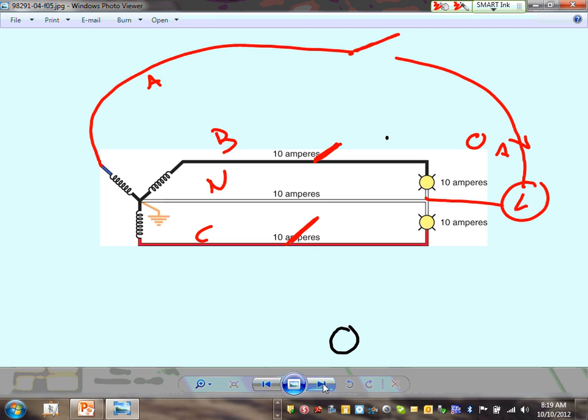It's getting more common to ditch the multi-wire branch circuits and just pull neutrals from the circuit, because nobody wants to have 3 circuits tied together in one circuit. I can't agree more. I'm an engineer, so pull as many conductors as you want. A lot of circuits are just getting their own neutral pull. After the code change, they stopped doing that because now everything has to have handle ties or 3-pole breakers.